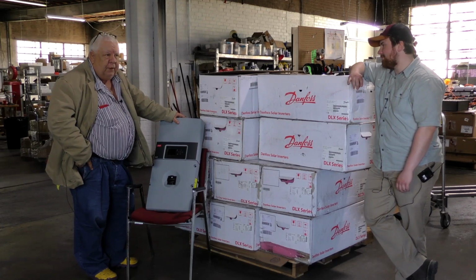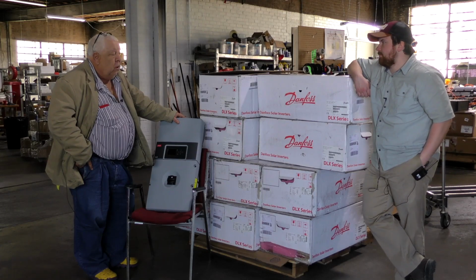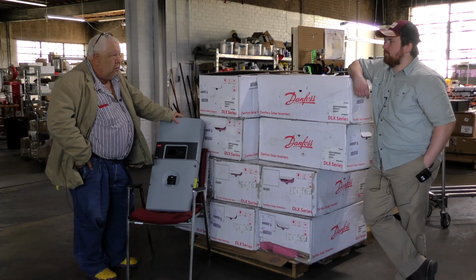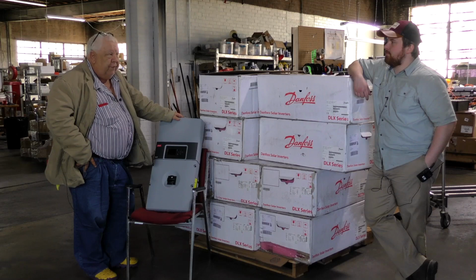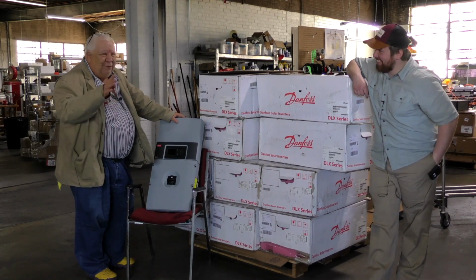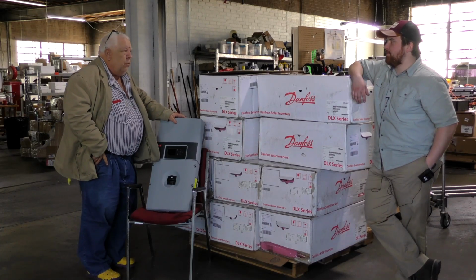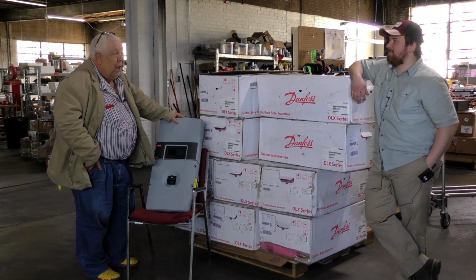There's another aspect. They've gotten very creative with their things. They want to do something called peak demand charges, and they have introduced this in the commercial end to fabulous success. They can take a company with a $100,000 a month utility bill and give them a discount from that bill if they'll just let them charge $250,000 a month. Such a deal. How this works is we'll give you a lower rate if you sign up to this program, but if you go above a certain peak demand level for more than 15 minutes, then you pay a higher rate. On page 56, you discover in 4-point type, it's a higher rate on the whole bill. 4-point type.